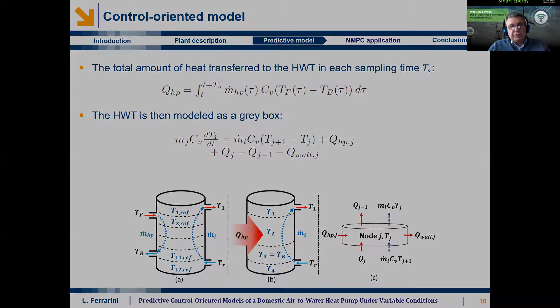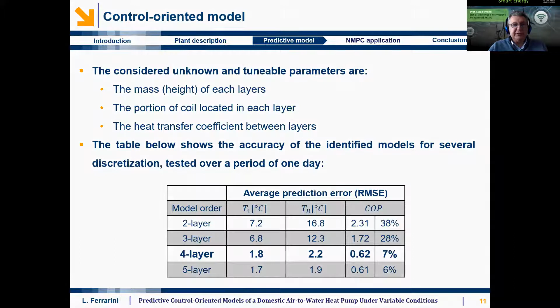And what we did is to try to understand how we have to distribute this heat between the layers and how many layers we should use with such a simple model of the system. As you can see here, there are errors in this simplification. And let me say, a good approximation is with a model of 4 layers with heat as an input and not mass flows as input, okay? And that's the typical errors that we obtain. So approximately a couple of degrees on the temperature inside the tank, which is an acceptable error. The temperatures are in the range of 40 degrees, more or less.